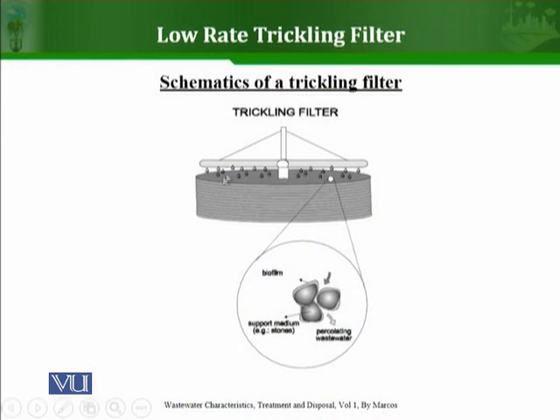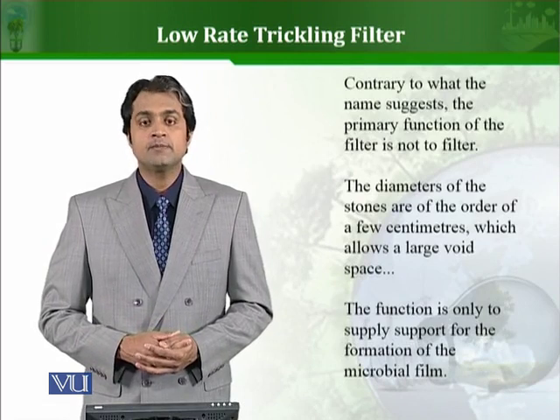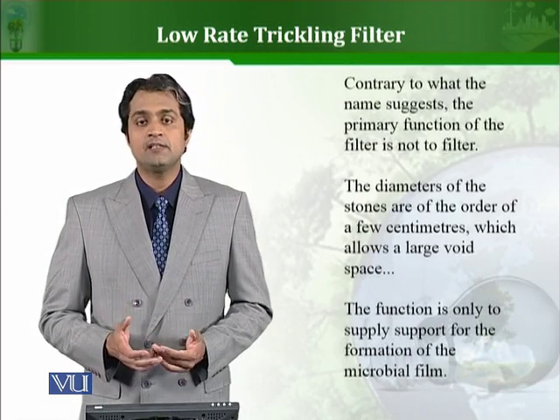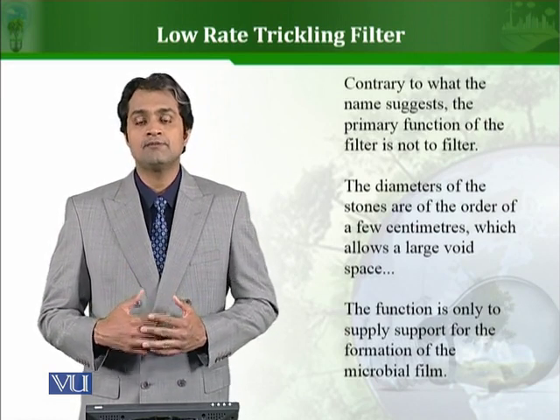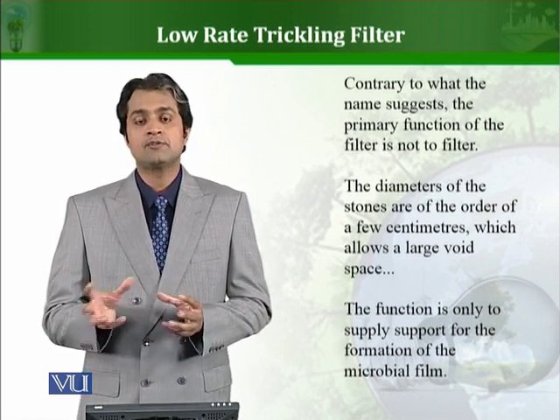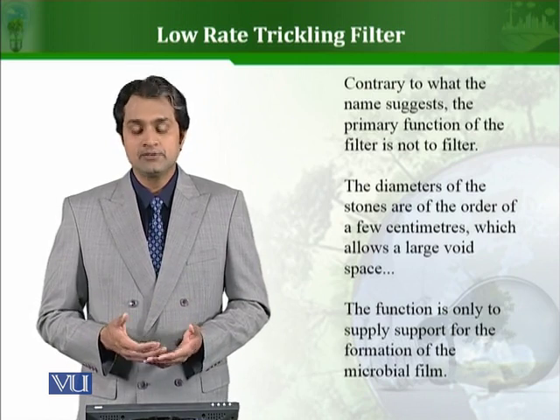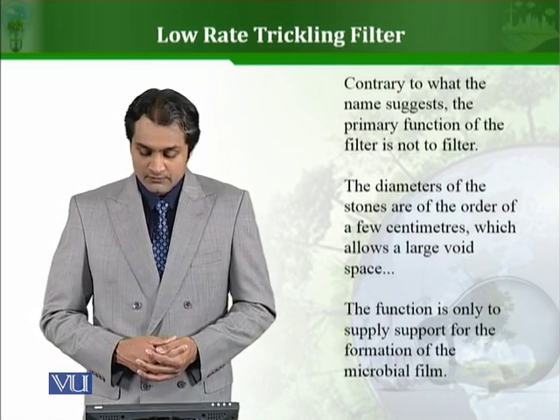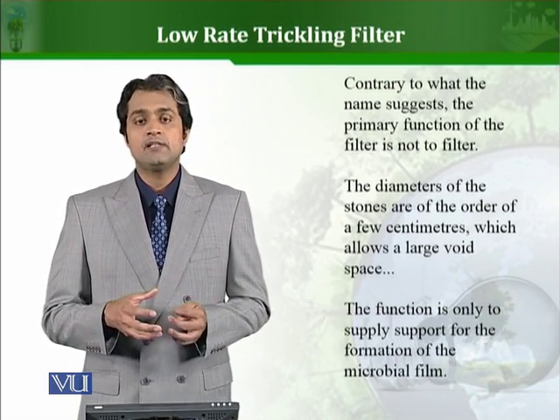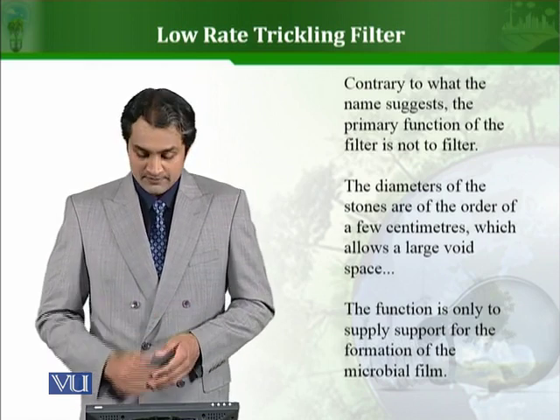This is the basic sketch of a trickling filter. You can see the support media, which provides support for the growth of the biofilms — it is a thin growth of microorganisms. When wastewater is applied, it contacts the bacteria and the organic content is degraded. Importantly, the name says 'filter' but the aim is not filtration — the spaces in the stone or gravel are too large for filtration. The basic function is only to supply support for the formation of biofilm, which then acts to stabilize the BOD present in the wastewater.